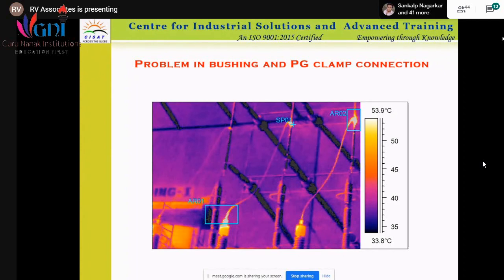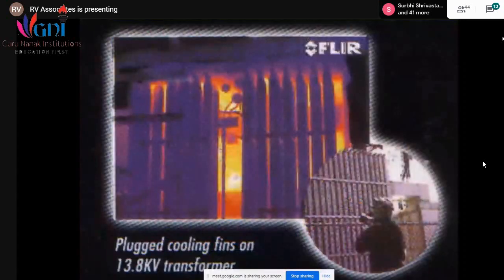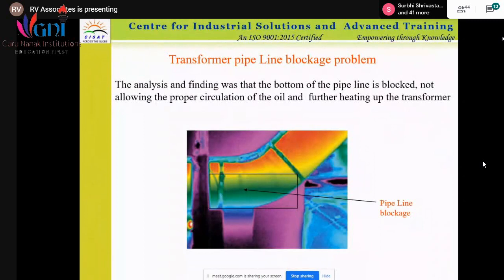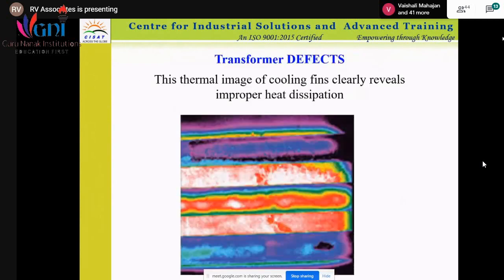This is the picture for the bushing, and parallel clamps are there in the case of substations where we connect it. It is a pipeline blockage, a pipeline blockage in the oil circulation in the transformer. If any such blockage is there, it is also indicated by the thermography.